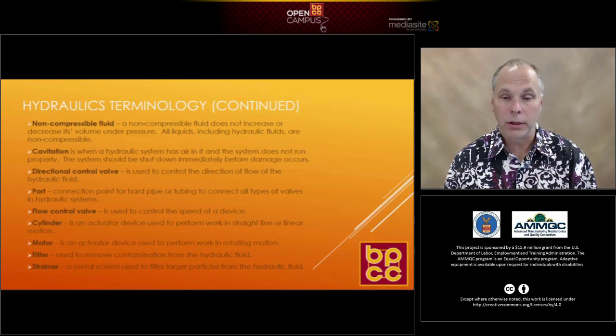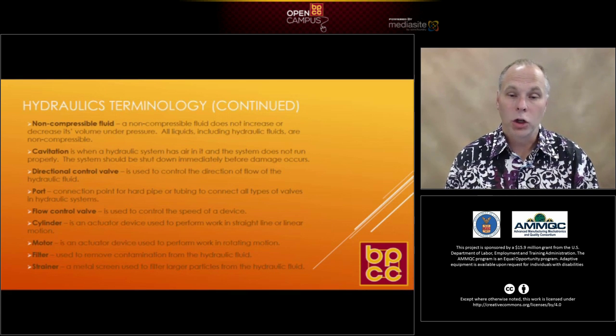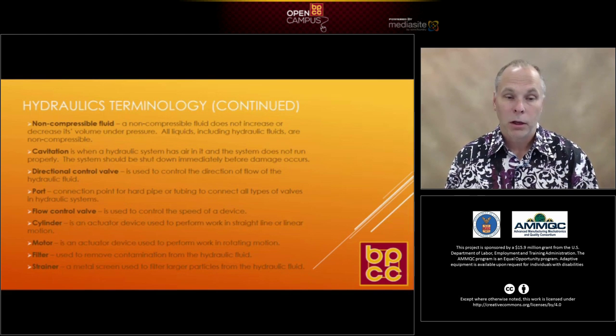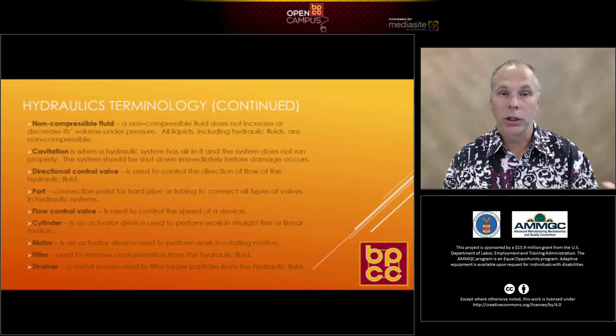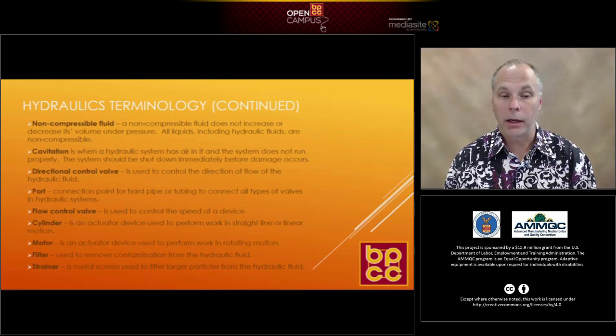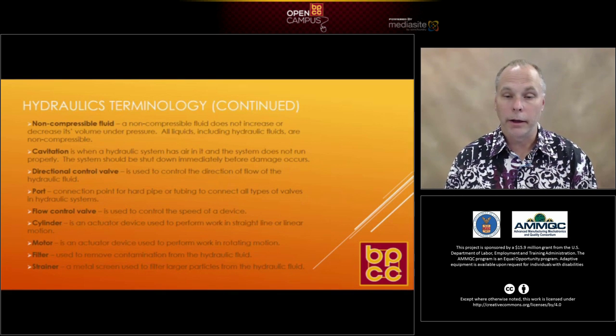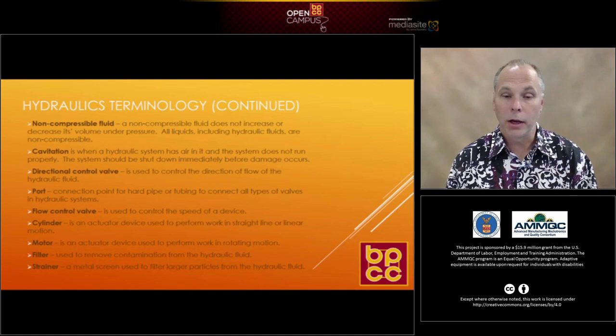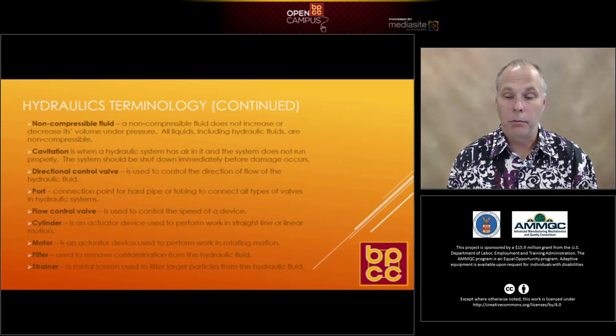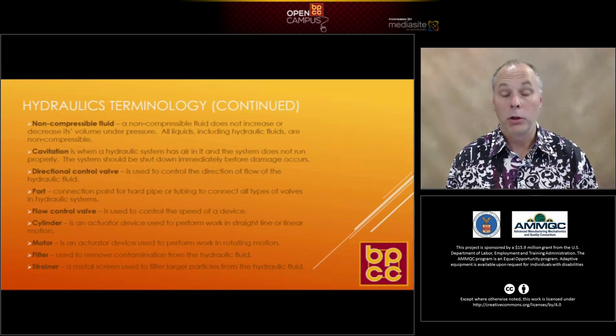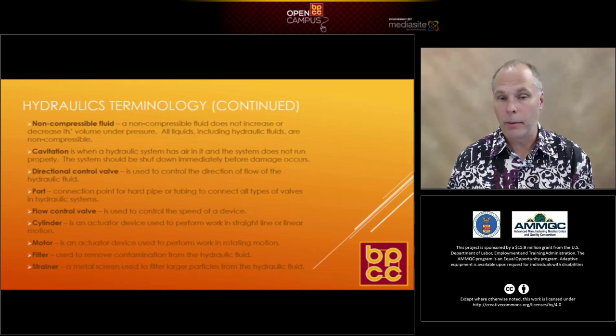Sometimes in hydraulic systems you end up experiencing what they call cavitation. It usually happens after somebody has worked on a piece of equipment and allowed air to get into the system. The air creates a bubble lock or causes something to happen — typically you'll hear banging and noises in a tube or directional control valve. The system should be shut down immediately so you can try to bleed the air out, which may be done on the maintenance side of manufacturing.